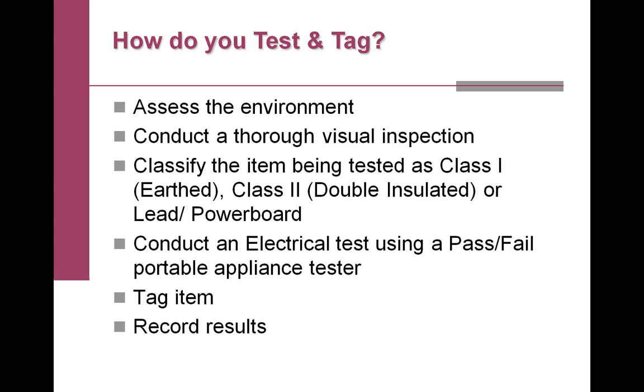Once the environment is assessed, there's a table within the Australian standard that dictates the test frequency based on where the item is located. People often ask, 'we've got a drill or a guillotine, how often does it need to be tested and tagged?' It depends on where it's located. If it's in what's classified as a non-hostile environment, not subject to dust, moisture or vibration, it may be tested as infrequently as every 5 years. But in a manufacturing environment with lots of moisture, dust and vibration, it would be a 6-monthly test cycle, basically meaning items more likely to be damaged need more regular inspection.